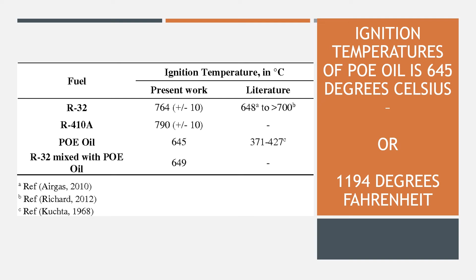Both refrigerants and oils have an ignition temperature. POE oil is used in 410A systems and has an ignition temperature of 1,194 degrees Fahrenheit. If the pressure increases the temperature above that set point and oxygen exists in the system, diesel effect will likely occur.